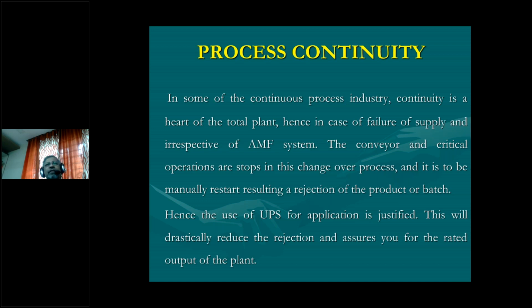So every process or application has to be understood. Hence, the use of a UPS for the application is justified. This will drastically reduce the rejection and assure the rated output of the plant. I'll give an example. In the old days, UPS were not in the picture. It was not popular, not yet introduced in India. I came across such an application.